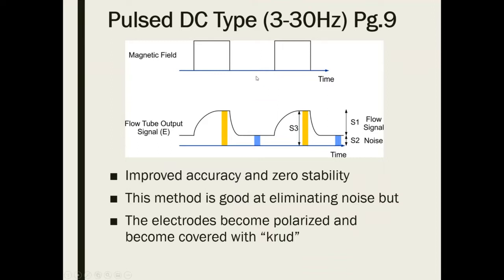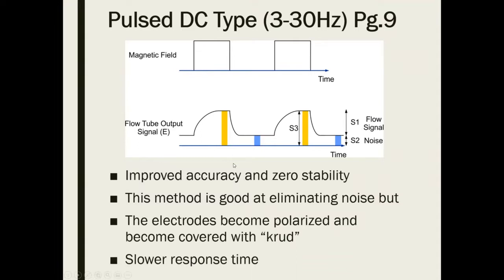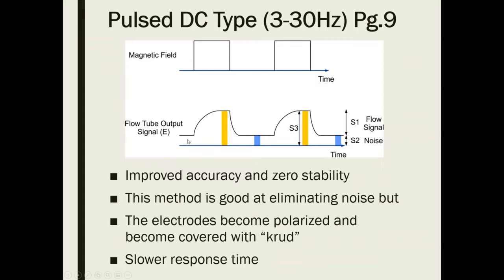A problem with DC excitation is polarization: because the voltage only goes in one direction, it attracts ions to the electrodes and they stay there since there's no reversing pulse to push them away. The electrodes become polarized and collect crud — that's the scientific term. This is the main problem with pulsed DC excitation. Also, these meters are a little bit slower compared to AC, since there are pulses with pauses between them.